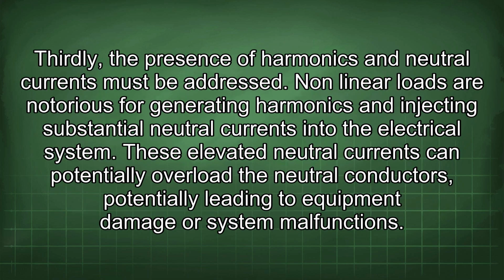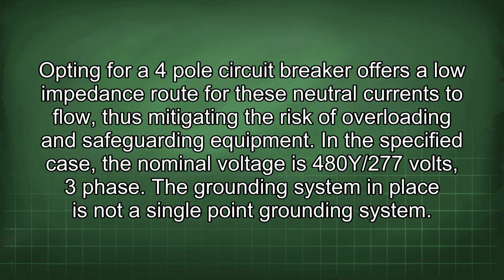Thirdly, the presence of harmonics and neutral currents must be addressed. Nonlinear loads are notorious for generating harmonics and injecting substantial neutral currents into the electrical system. These elevated neutral currents can potentially overload the neutral conductors, potentially leading to equipment damage or system malfunctions. Opting for a 4-pole circuit breaker offers a low impedance route for these neutral currents to flow, thus mitigating the risk of overloading and safeguarding equipment.